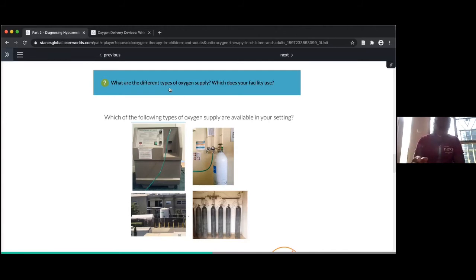For the cylinder, as Dr. Papito is saying, some people don't check the manometer to see how much oxygen is left. Some of my porters will take the cylinder and try to feel if it's heavy, and they think if it's heavy, there is oxygen inside. No, you need a manometer to check your cylinder and see what the pressure is in it. That's how you check. You don't check it by lifting it and feeling if the weight has increased. Those are the small things you need to install in your service, so people will know how to check if the device is functioning or not. It's very devastating when you need oxygen and you find the cylinder is empty.